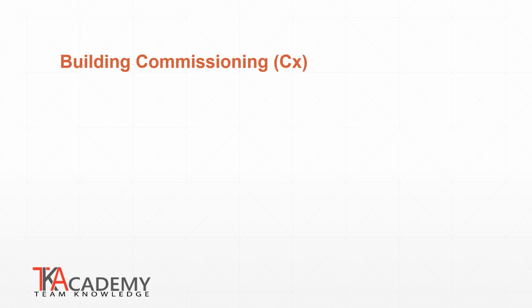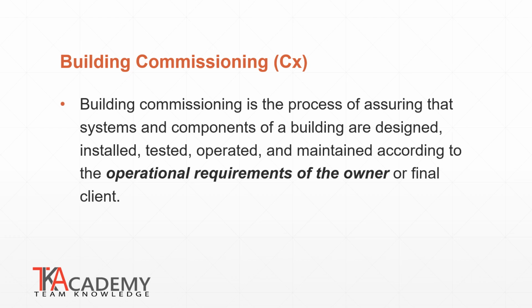We have established that the term commissioning comes from launching naval ships, but how does this apply to a stationary building? What systems are commissioned in a building? Building commissioning is a process of assuring that systems, equipment, and components of a building are designed, installed, tested, operated, and maintained according to the operational requirements of the owner. Essentially, any part of a building can be commissioned, but the focus of commissioning services tends to be on the operational systems and those components that influence building performance.